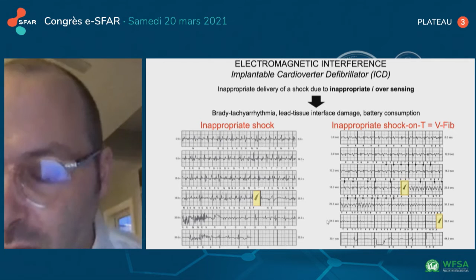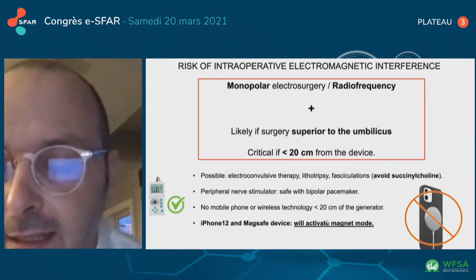To estimate the risk of interference, mainly two factors are important. The first one is the use of monopolar electrosurgery, and the second one is radiofrequency. This risk will be very likely if the surgery happens superior to the umbilicus, and it will be critical if it happens less than 20 centimeters from the device. We should also know that we can use a peripheral nerve stimulator for local regional anesthesia. This is safe. And take special care with mobile phones. Usually the recommendation is not to use a mobile phone next to a generator. This is specifically true for the latest generation iPhone 12 and MagSafe devices, which will simply activate the magnet mode, meaning that they will inactivate ICDs. This has been well described in a recent case report.